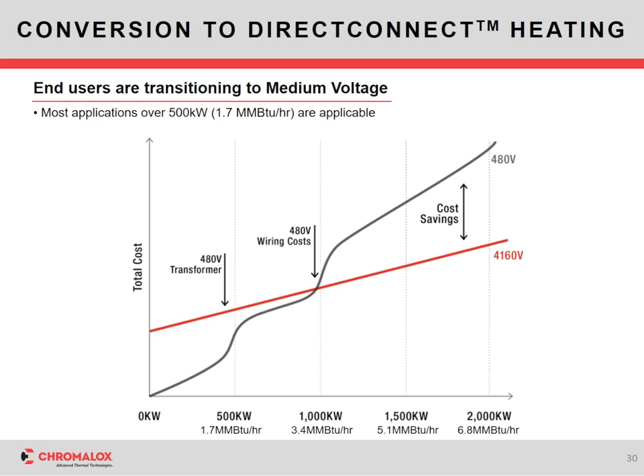Now, when does it make sense to use a medium voltage system? If you remember the chart I showed earlier with the traditional low voltage market versus a gas fired system versus a medium voltage, well, generally speaking, medium voltage depends a lot on the wiring cost and on the on-site. So just to look at it from a product standpoint, around 1 megawatt worth of heating need is when it begins to make sense to use a medium voltage system. Now again, there may be other concerns like permitting, emissions or pollution stack that start to change that. But these are some rules of thumb to help guide you for a medium voltage system.